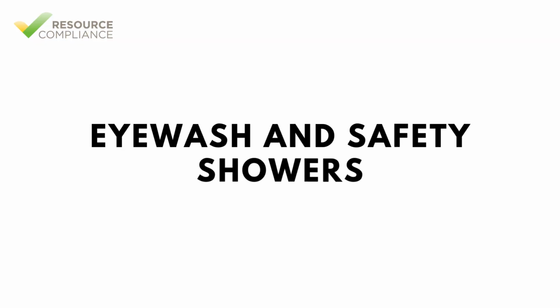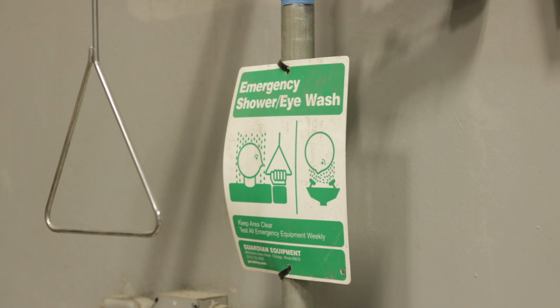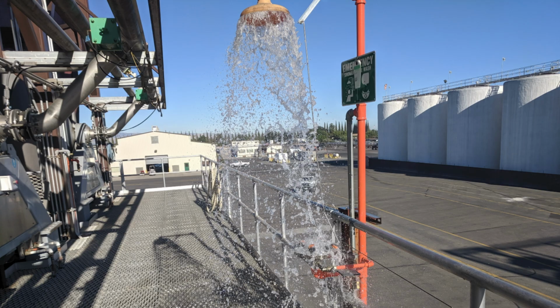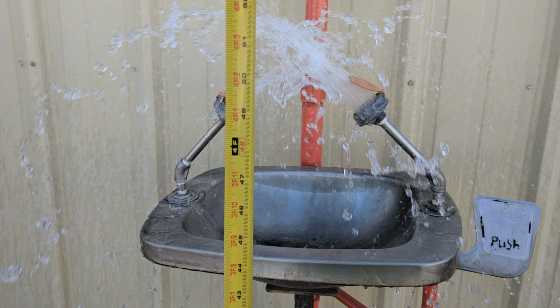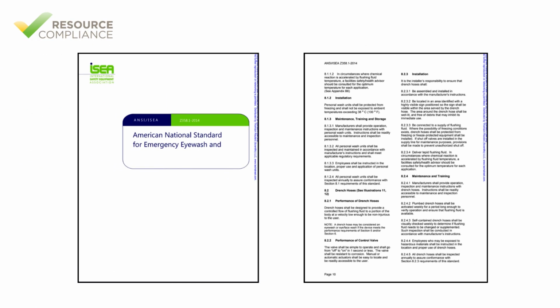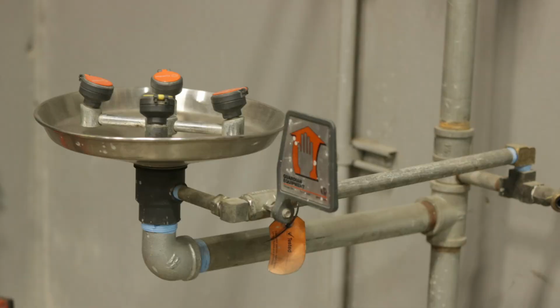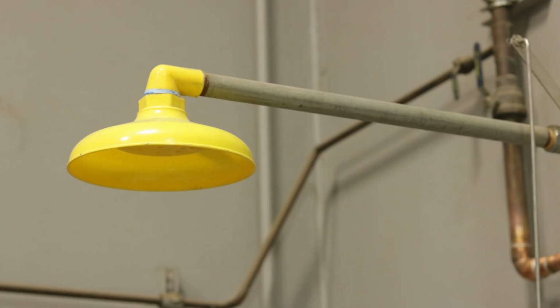Eye wash and safety showers are important resources for administering first aid. As such, the combination units serving the refrigeration system should be tested weekly to flush the lines and ensure water flow is adequate. Annually, these units should undergo a more thorough test to ensure the units are installed in accordance with ISEA Z358.1. Among other things, the annual test will check for proper flow rate, flow pattern, and water temperature.